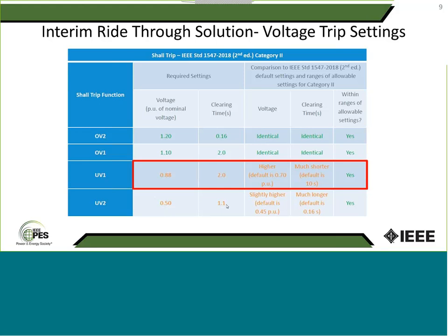So with all these settings, let me explain the distribution utilities' resistance towards adopting ride-through. When I say resistance, there's a technical reason for that. On the distribution side, the DERs, well, let me rephrase that. If you have an under-voltage condition and the DER senses that, it's supposed to ride through up to a certain limit. If that under-voltage is caused by a fault on a transmission system, like the bulk system, then the DER has to ride through that under-voltage condition. But if that under-voltage is caused by a fault on a distribution wire, then the DER should trip.